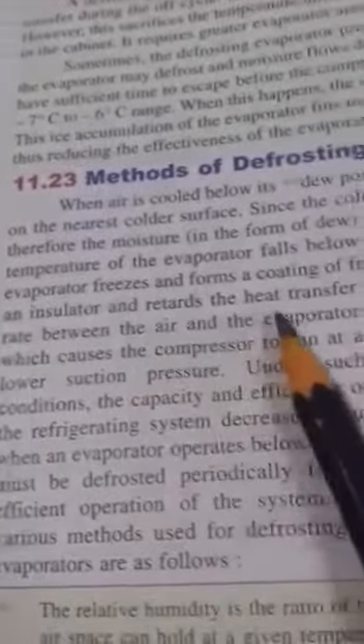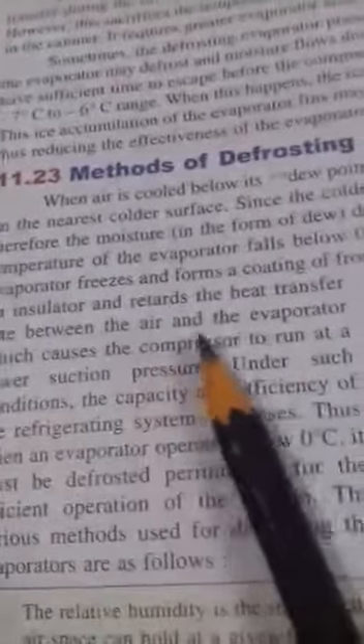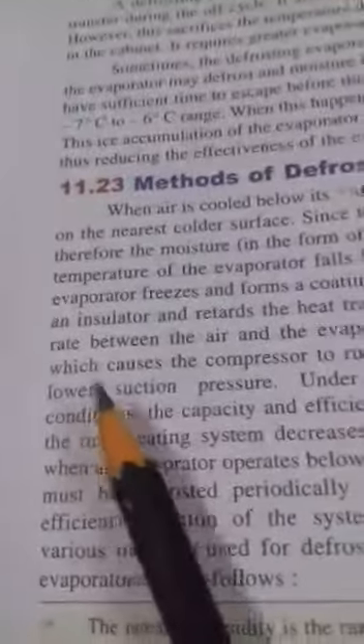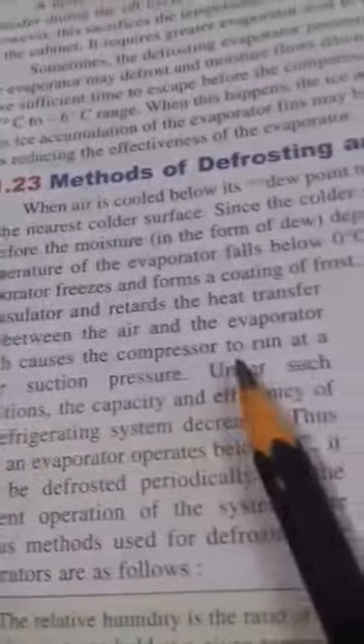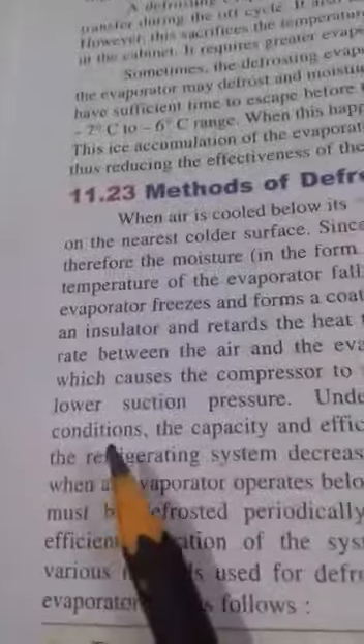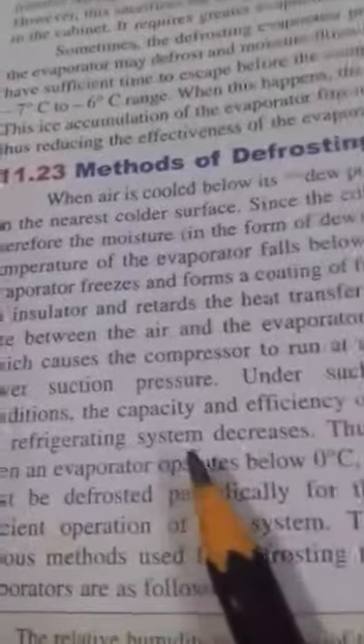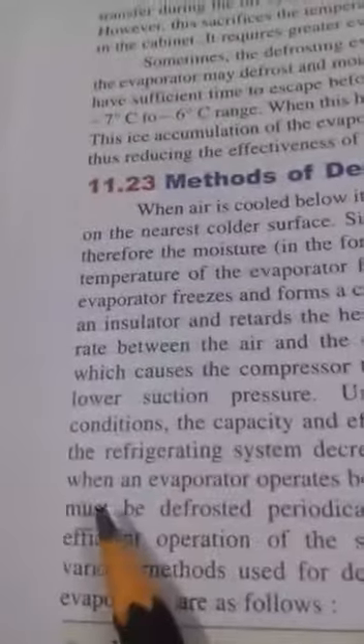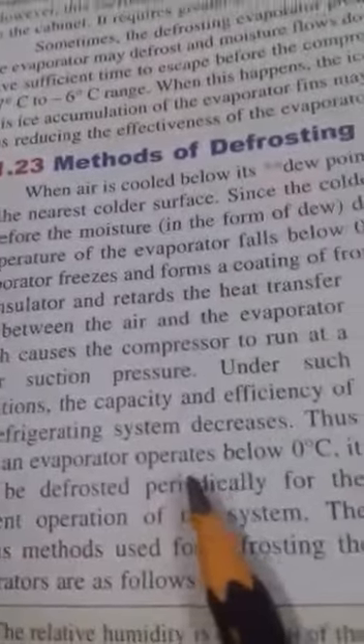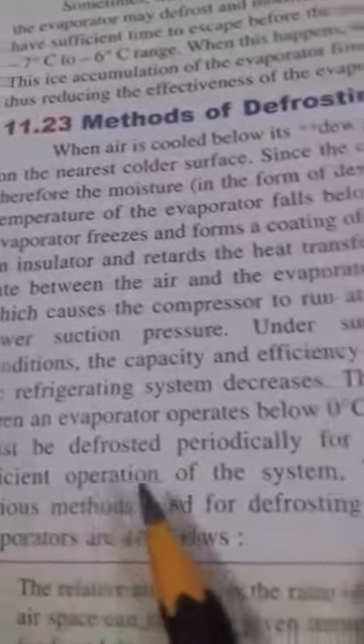If this frost is not removed periodically, it acts as an insulator and retards the heat transfer rate between the air and the evaporator, which causes the compressor to run at a lower suction pressure. The capacity and efficiency of the refrigerating system decrease. Thus, when an evaporator operates below zero degrees centigrade, it must be defrosted periodically for efficient operation of the system.